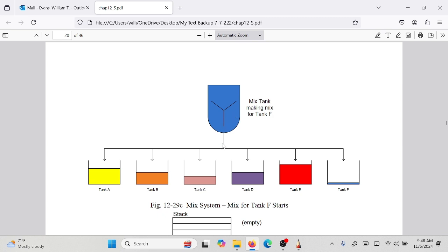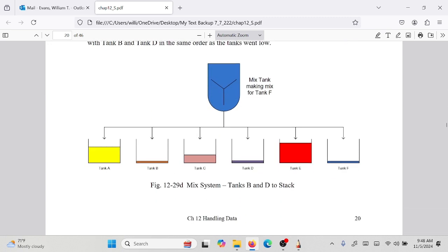Now in the meantime, more of them come low. In other words, 2 of them come low. And when those hit, they hit in the order that they actually went low at. So in other words, you queue up just like you would in a grocery store. That's what a FIFO instruction does. If you were to write all those instructions without the FIFO instruction, it would take you quite a while. So they give you these specialty instructions just for this application. This is a queuing application. Okay, FIFO load, FIFO unload. And if you ever get into that situation, that's what you would do.